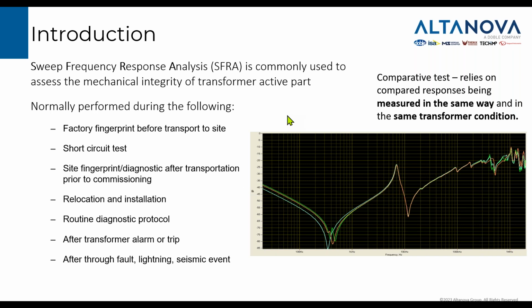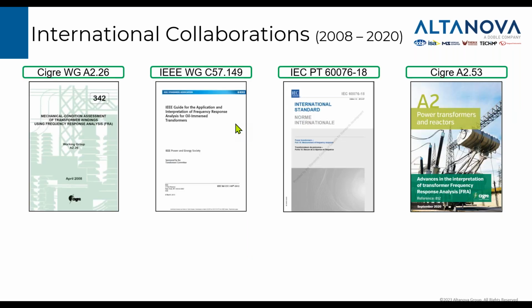I will talk about them later. When we suspect something has happened to the transformer, that it could have deformed, in order to have reference results, we should also do it. We recommend doing it as a routine test on a transformer when it is on site, or at least, if not routine, once in a lifetime after installation on site. It is also often made as a factory fingerprint in the factory during FAT tests. It can be done before and after a short circuit test, or before and after relocation. So whenever we expect something could have happened to the geometry of the windings, it's good to do it, and it's good to have a good reference from the past, so it could be planned prior to any happening to carry this out.